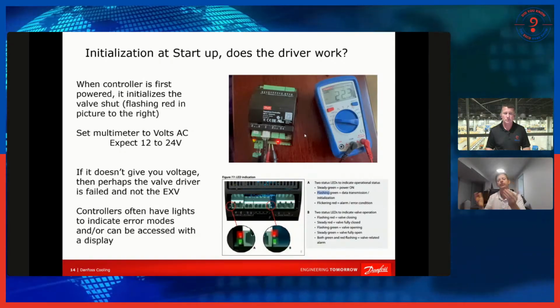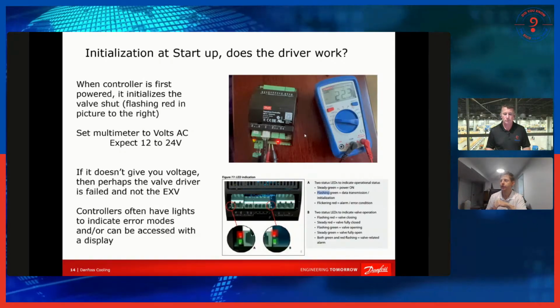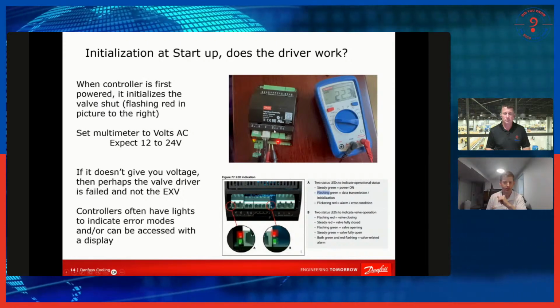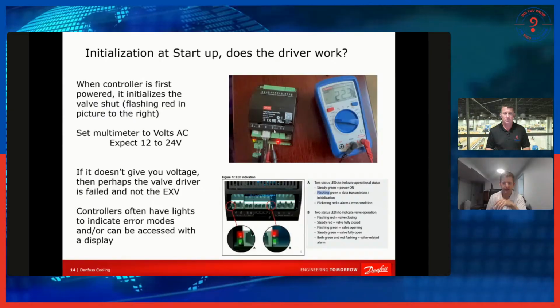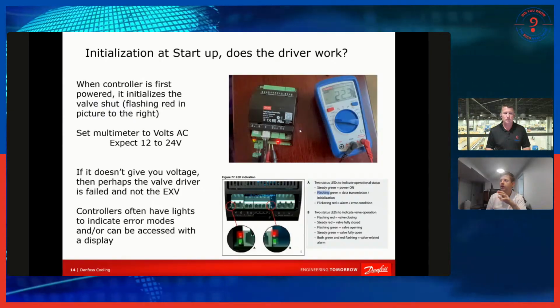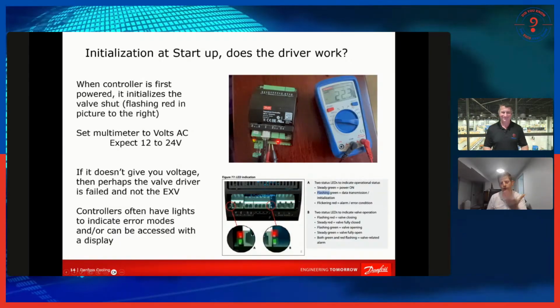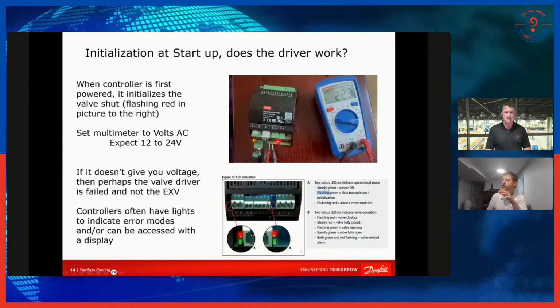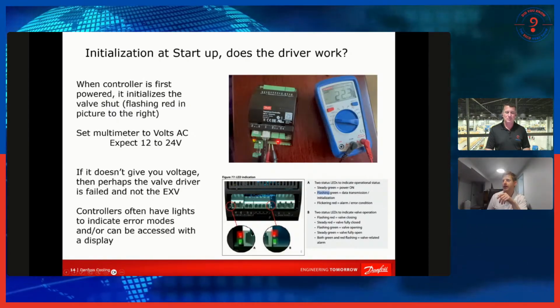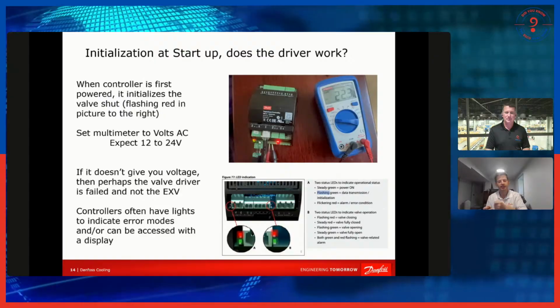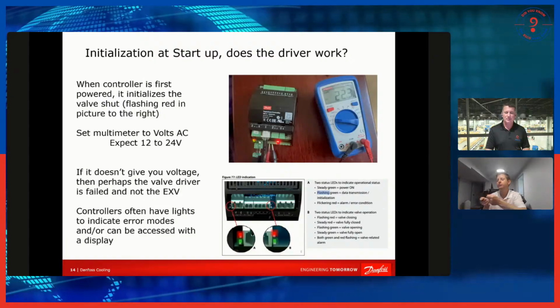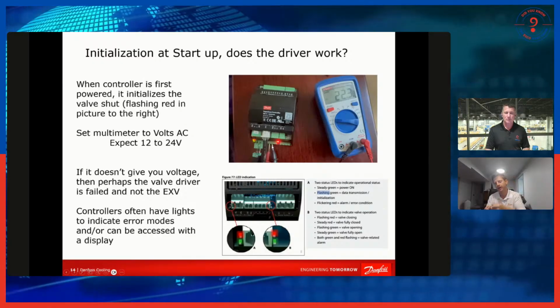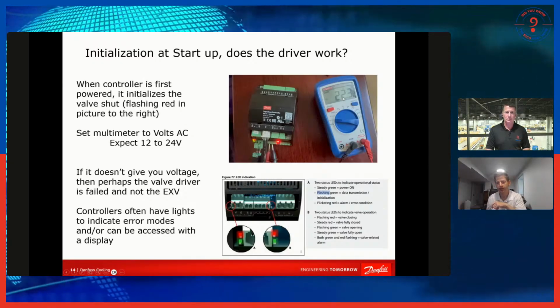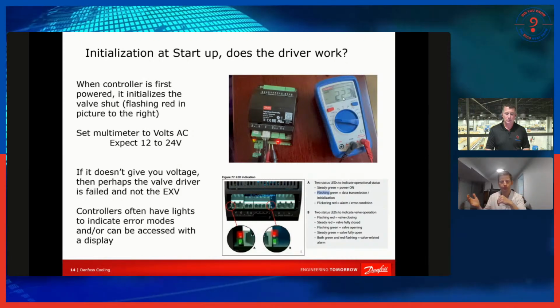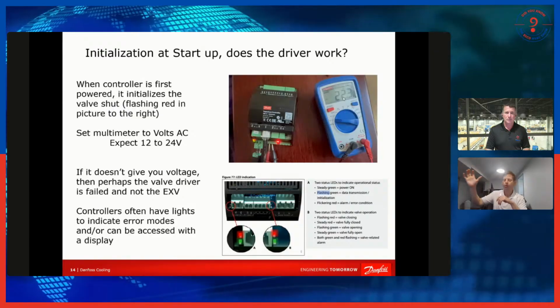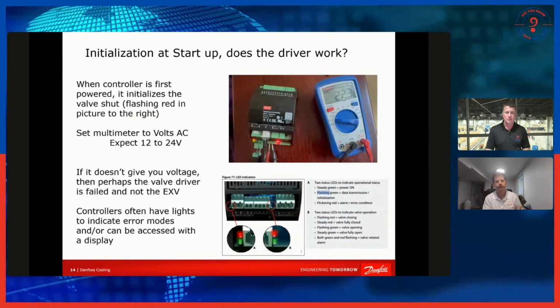Is there a problem with the controller? If you pull power to your EXV controller, it's probably good to do this when the system's already shut down, so you're not cutting out the suction pressure to it. The system is off, but the controller is still operating independently. You can pull power to your controller, plug it back in, and then set your multimeter to volts AC and put it on two of the terminals where power goes to it, and look if you're getting voltage. If you're getting voltage, generally between 12 and 24 volts, that's an indication that my controller is at least providing power to the EXV.